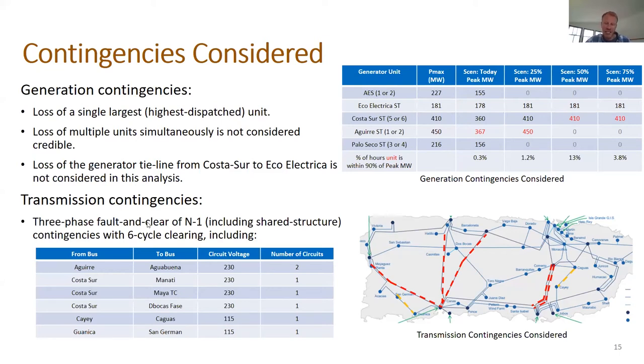On the transmission contingency side, on the bottom, you can see a table. We looked at six different line outages. This is where there would be considered a fault or a short circuit on that transmission line in the island. And subsequently, the protection systems on the island would suddenly remove that transmission line from service to clear the fault, leaving the grid to operate with one transmission line down.